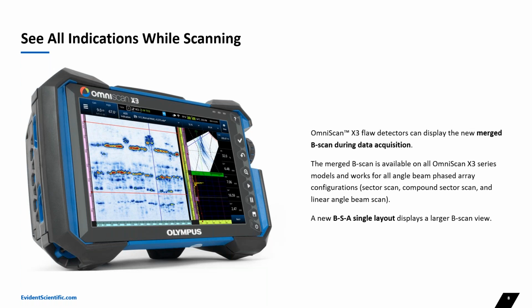If you're performing manual phase array weld inspection, we actually added a new layout. We call it BSA, B first, because the B-scan takes the most place on the screen, like on that picture. The reason is that the taller image with the merge B-scan just makes interpretation a little bit easier than if it was squeezed vertically. So we decided to go ahead and create that new layout, which is especially handy for acquisition.